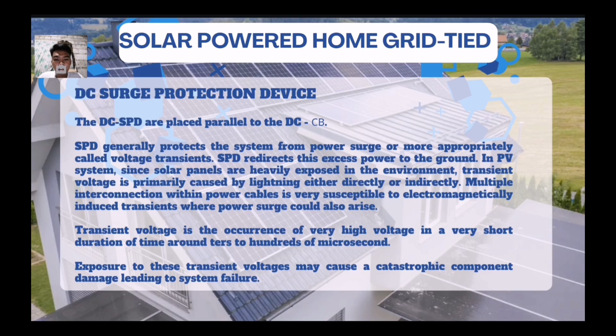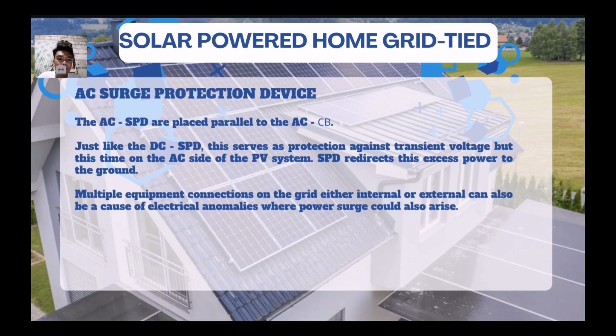The AC SPD is placed parallel to the AC circuit breaker. Just like DC SPD, this serves as protection against transient voltage, but this time on the AC side of the PV system. SPD redirects this excess power to the ground. Multiple equipment connections on the grid, either internal or external, can also cause electrical anomalies where power surge could also arise.